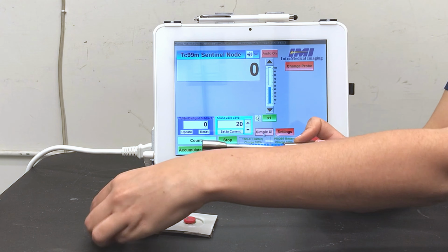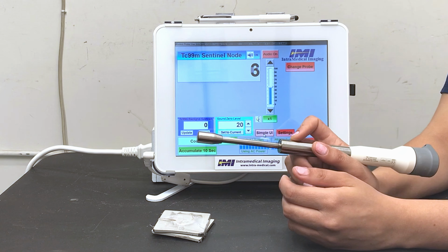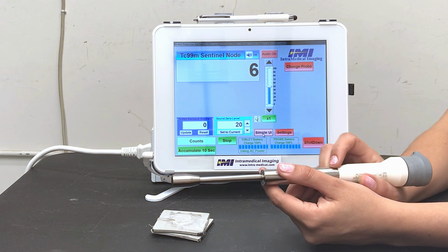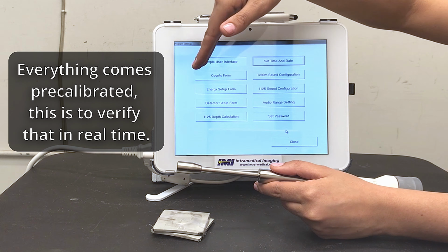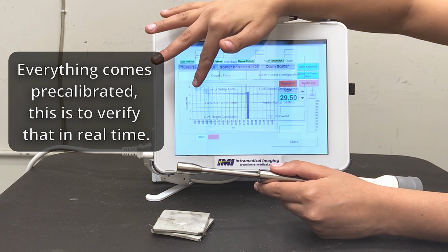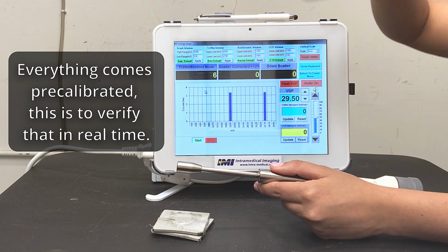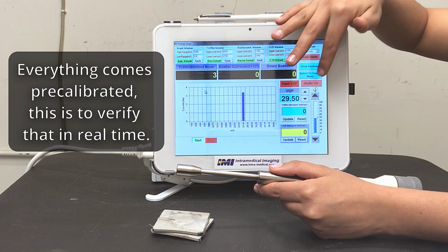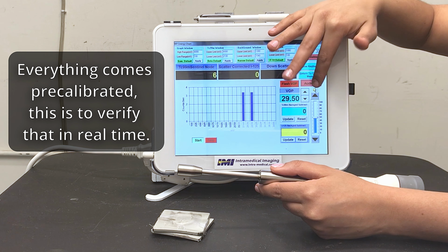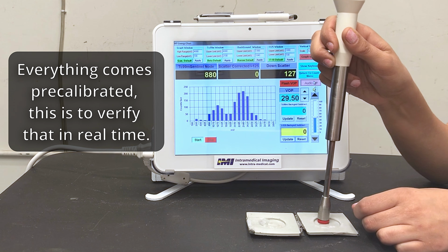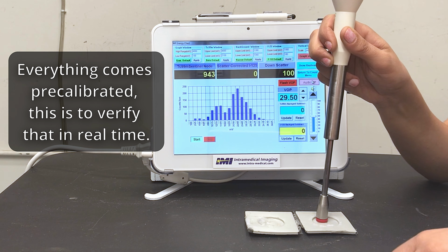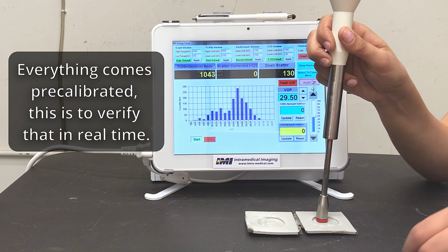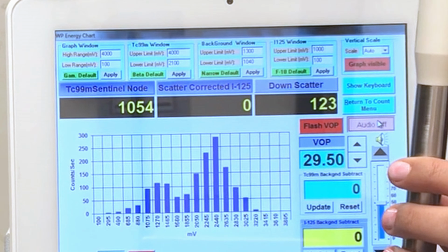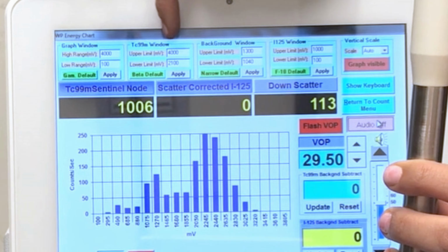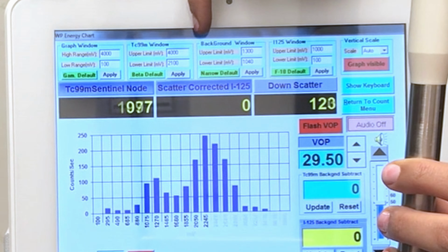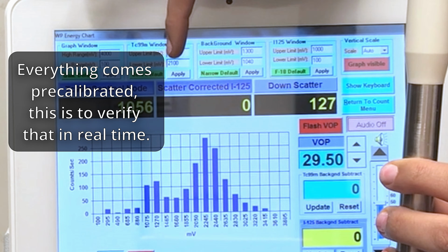To see the probe's detection capacity in real time, select the red Settings button above the battery life display. Select Energy Setup Form to view important voltage settings. Mute the sound by pressing the red Audio On button. Then place the probe on the source. The graph should show 2 peaks, indicating the optimal range of energy that TC99 will emit. The ideal energy window for TC99 is between 2100 and 4000 millivolts.